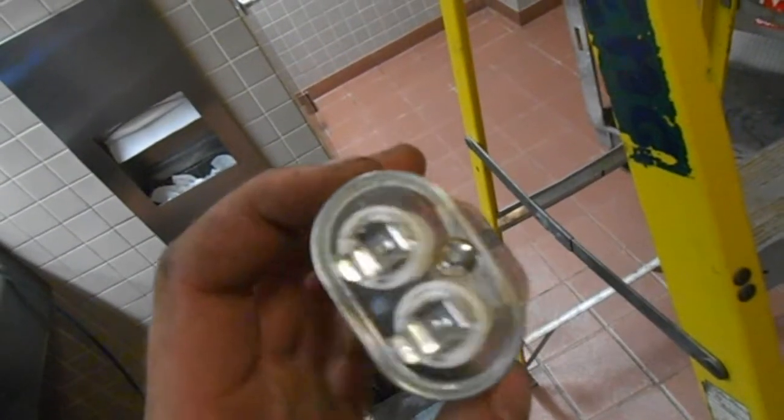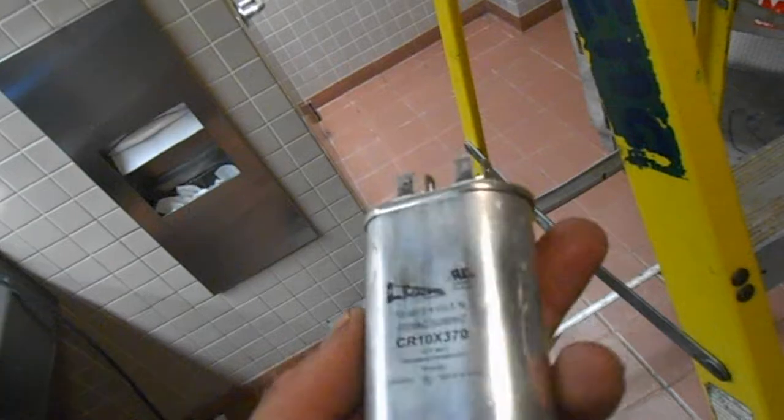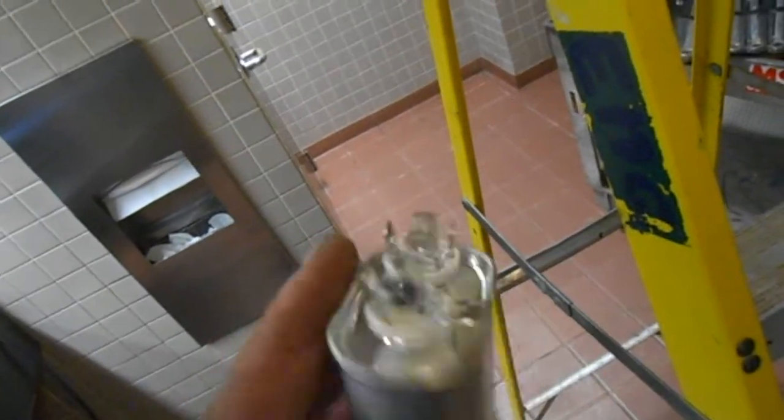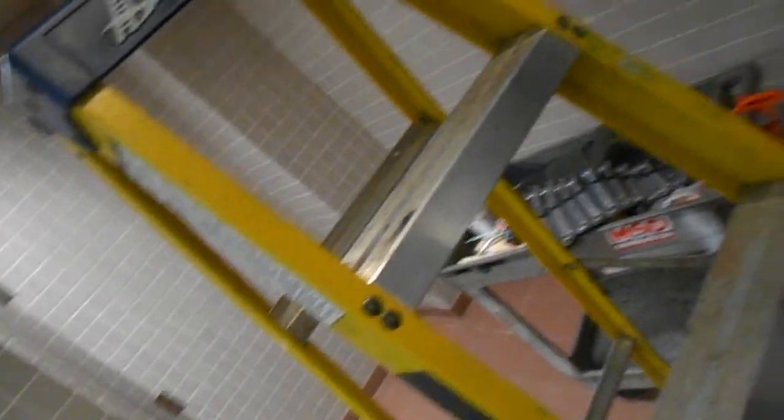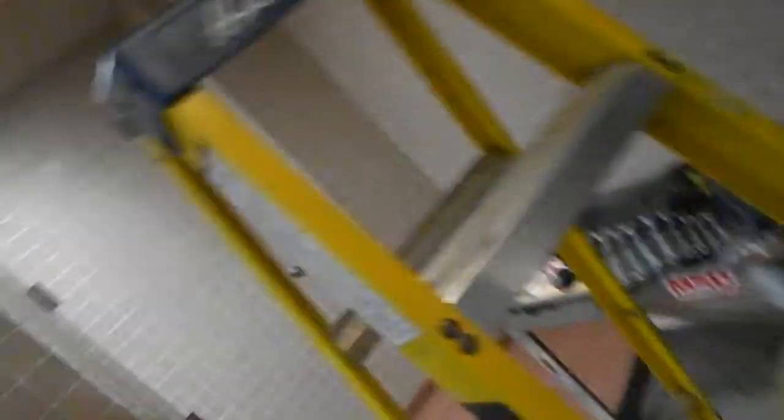Been here before, replaced a couple of bad electrical components, control transformer and blower relay, and also replaced this fan capacitor. Maybe 3 or 4 months ago, maybe a little longer. Anyways, the capacitor is blown again. I've got zero microfarads on it.